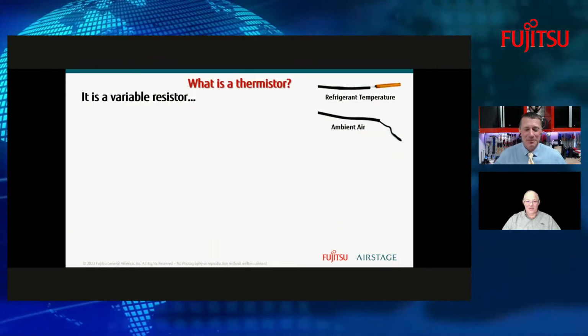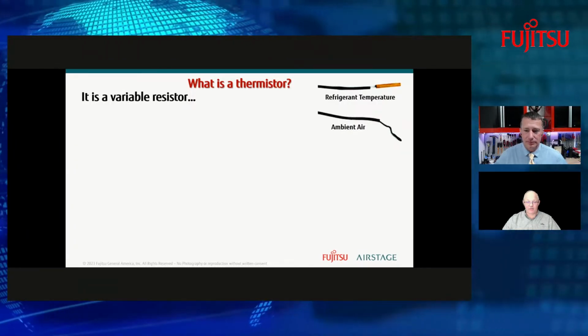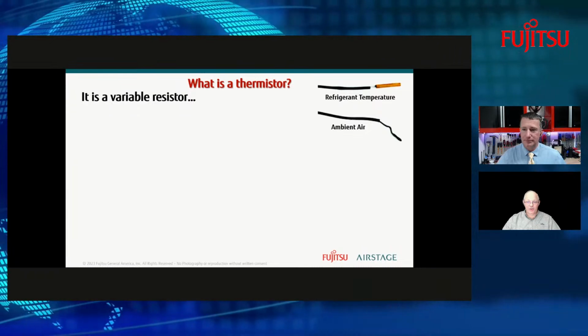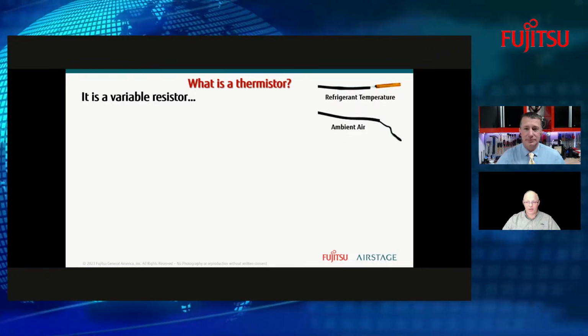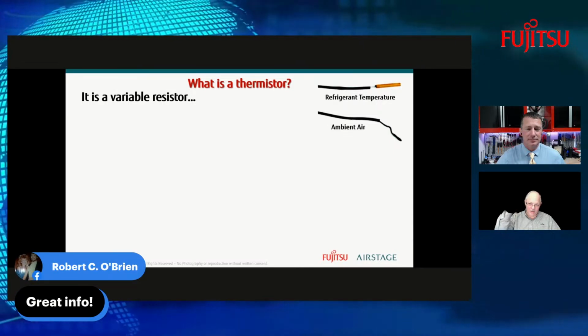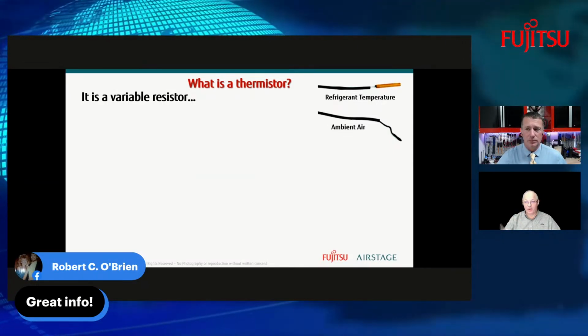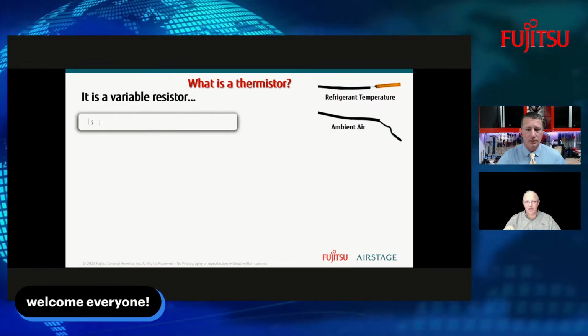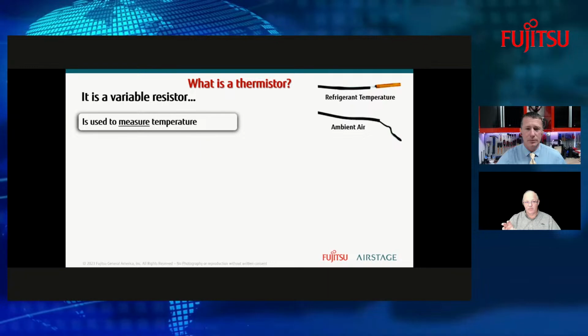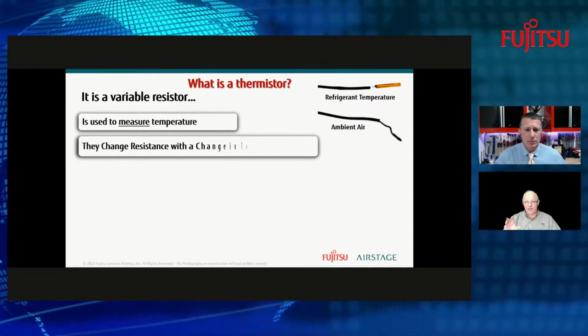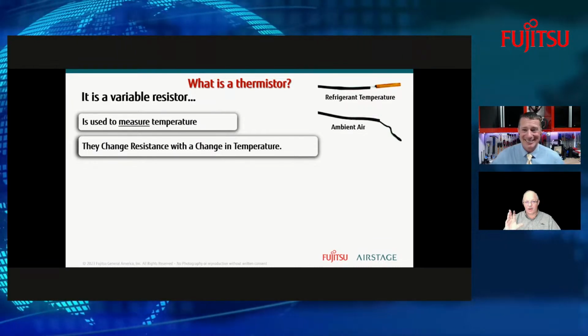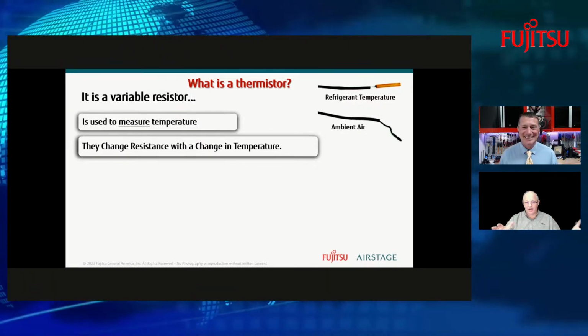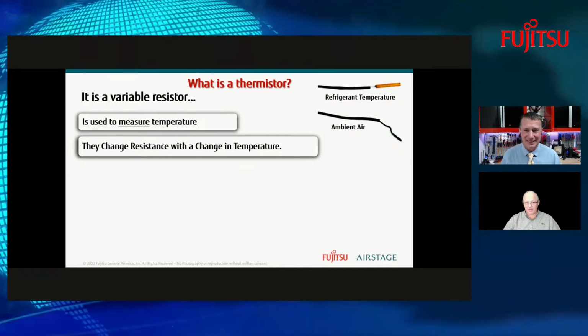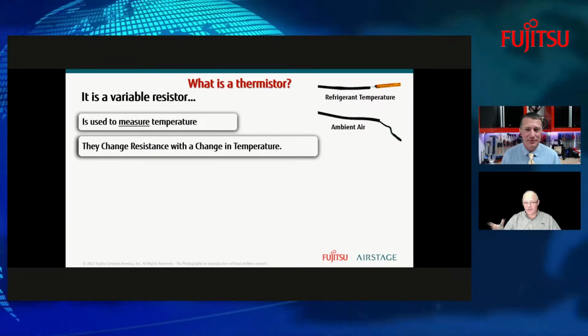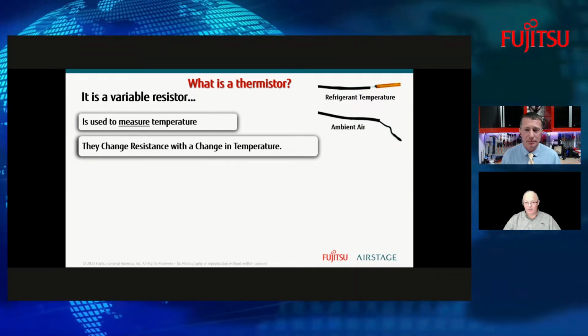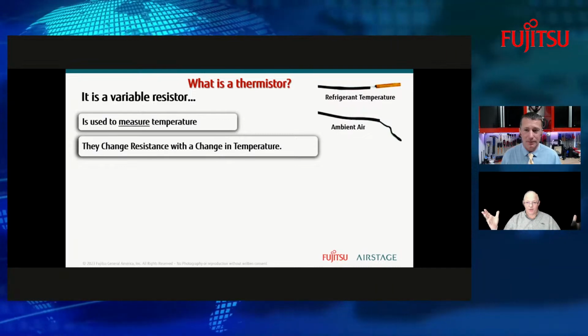All right, so let's talk about our thermistors. This is the indoor thermistors you're looking at right here. In the upper right, the refrigerant temperature, it's got that little copper barrel. It actually fits down into a little bitty well that checks that temperature coming in. Then we have the ambient thermistors. So the system is looking at these resistors. These are the king of how the system works. You could easily have up to 9 of these in a system. If you don't have them, the system would not know where you're at and what you need. It would just be like, well, I don't know, I just have to go full out.